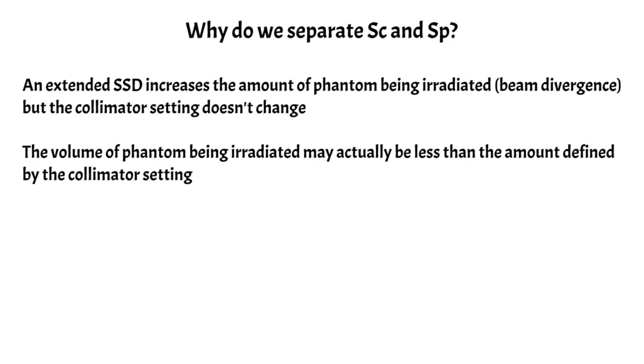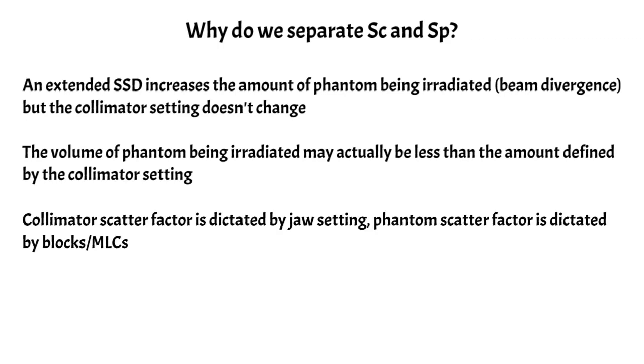Why do we need to separate the collimator scatter factor from the phantom scatter factor? There are a few situations that make this clear. One is if we have an extended SSD — this increases the amount of phantom being irradiated due to beam divergence, but the collimator setting doesn't change, so we need to account for that differential volume by using a different field size for the phantom scatter factor. On the flip side, the volume of phantom being irradiated might be less than what the collimator defines — for example, a block or MLC shaping the field so the field size at the phantom surface is less than the collimator setting. Because of this, we use two different field sizes: collimator scatter is dictated by the jaw setting, while phantom scatter is dictated by any blocking or MLC field shaping present in the beam path.